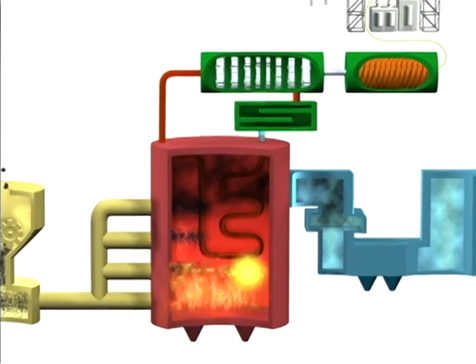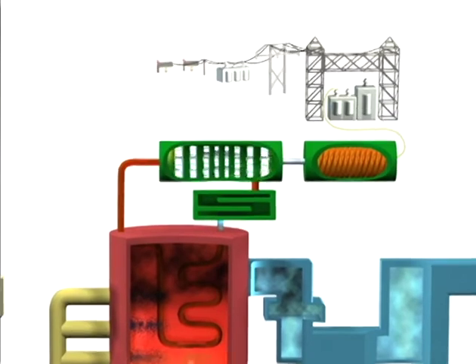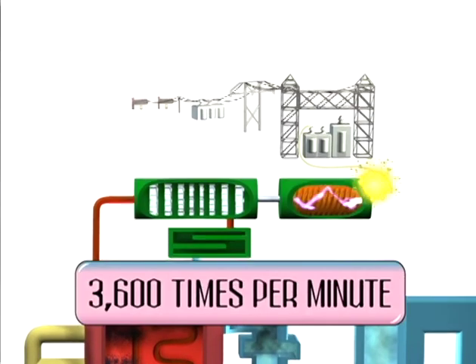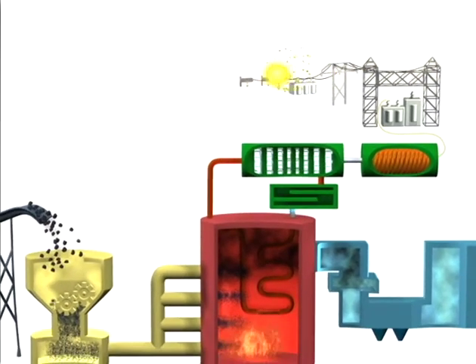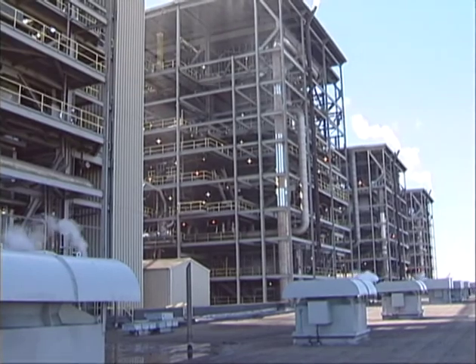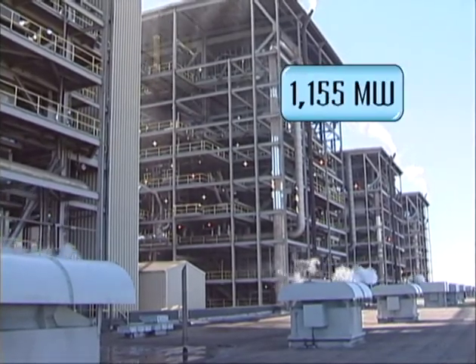From the boiler, superheated steam races through the pipes at 1,000 degrees Fahrenheit, where it's forced under very high pressure through the blades of the turbine, turning the blades at 3,600 times every minute. The turbine then turns the magnet inside the coils in the generator, which produces electricity.